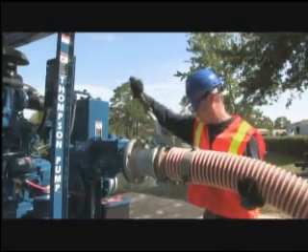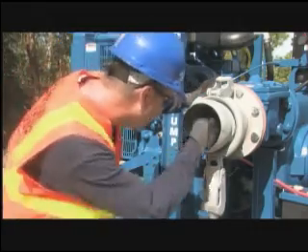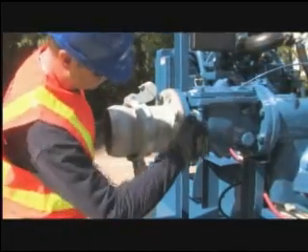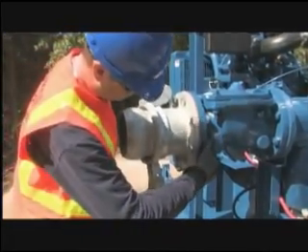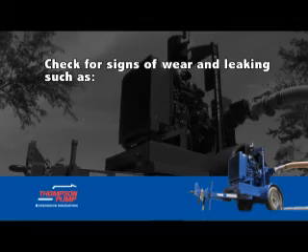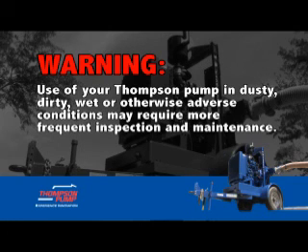Inspect the pump's hose connections and clamps to make sure they are not loose or damaged. Check the discharge priming valve. Gaskets and O-rings should be smooth to the touch upon inspection. Check nuts and bolts on all fittings and mounting feet for tightness. Check for signs of wear and leaking, such as spots on the block, pump, priming system, or the frame. Warning: use of your Thompson pump in dusty, dirty, wet, or otherwise adverse conditions may require more frequent inspection and maintenance.